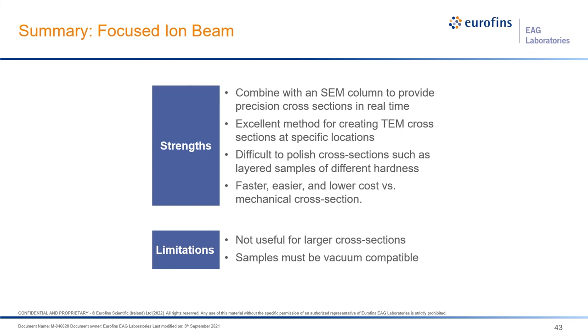Limitations of FIB: not useful for larger cross-sections. Typical dimensions are 20 microns wide and 10 microns deep, though we can go larger and deeper — time is money. The newest next-generation focused ion beams have capabilities for larger cross-sectioning using xenon gas instead of gallium. Samples must also be vacuum compatible.